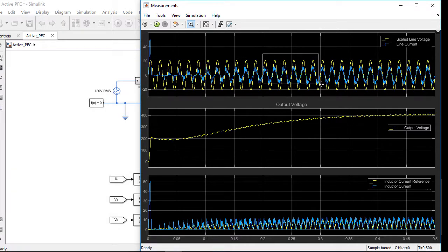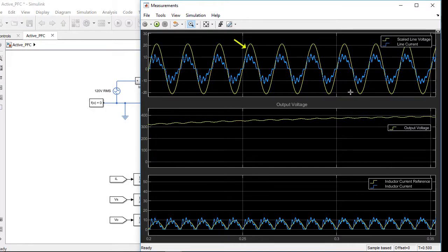In this plot we see the line voltage in yellow, the line current in blue. The current waveform shows the presence of harmonics which results in a poor power factor. We will therefore need to retune the controllers for a better power factor correction.